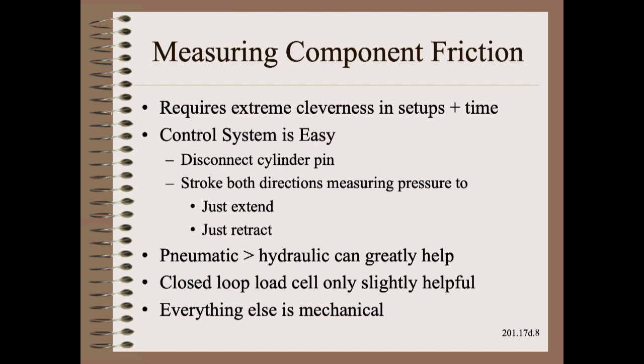If we decide to redesign, we need to know how much friction is coming from each of the many elements in the mechanical control system, so that our new design addresses the worst ones. The control system contribution is the easiest to find. Simply disconnect the cylinder pin and stroke the piston in both directions, while measuring the pressure required to just extend and then to just retract. Some of this uncertainty is regulator or E-to-P hysteresis, which can be found in the valve performance specs or by direct measurement. The bulk of the rest is the piston seal. Going from pneumatic to hydraulic can greatly help in these component frictions.